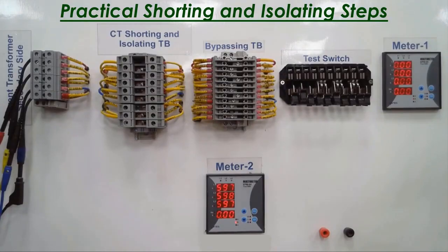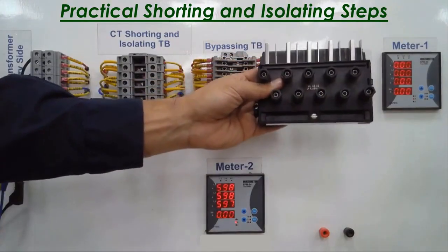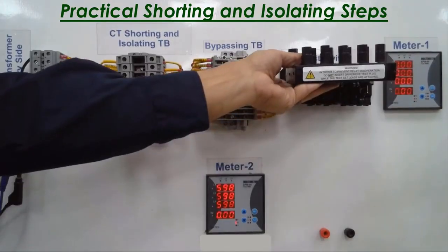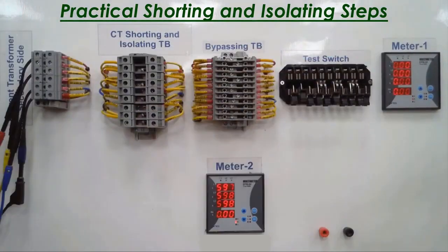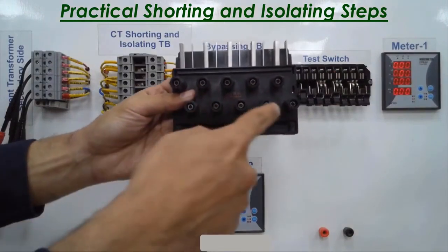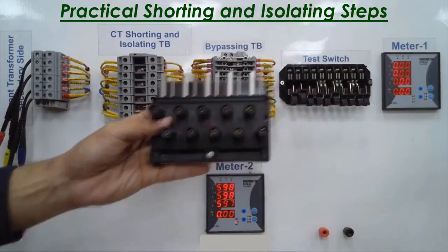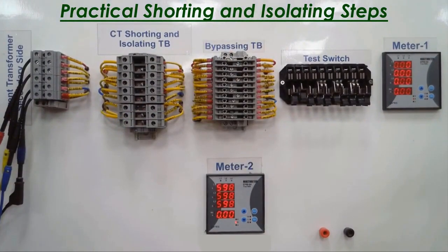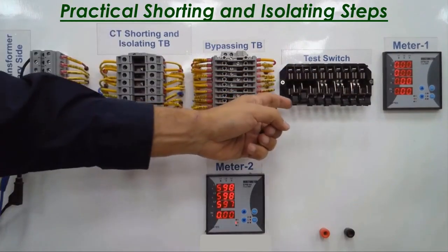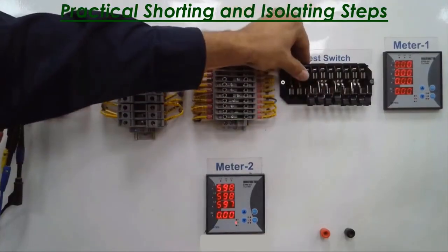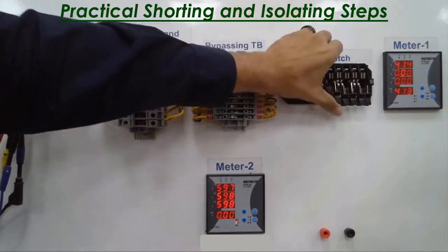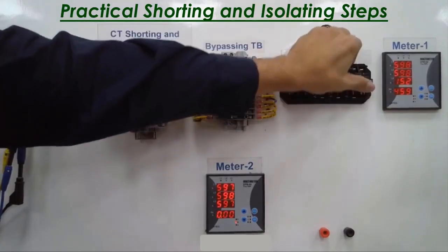We agreed that to do isolating, you need to bring your test plug and ensure you are entering the test plug here to isolate the first power meter, and then you connect your test leads here to test your power meter, or if it was, of course, a protection relay. Why do I place the metallic test plug and open all the fingers together? This is the third topic I wanted to talk about. The idea is quite simple, guys.